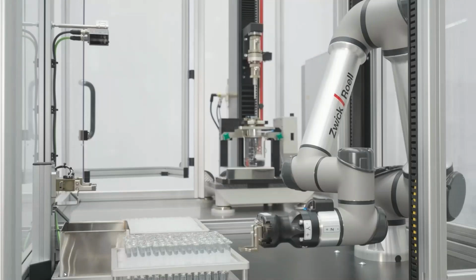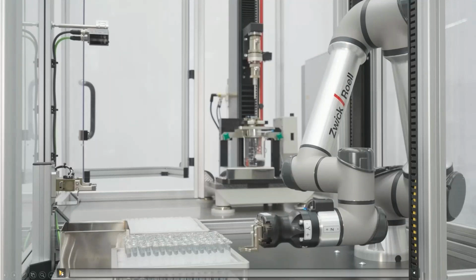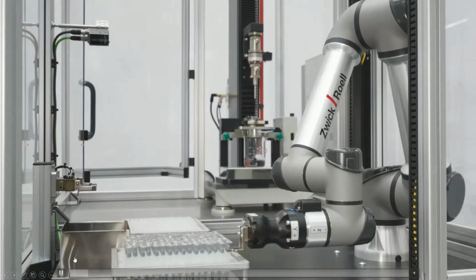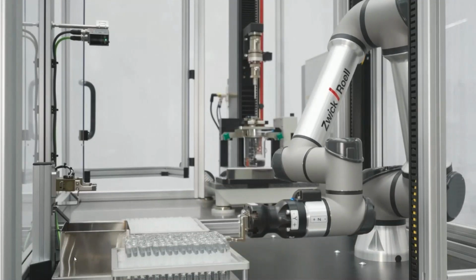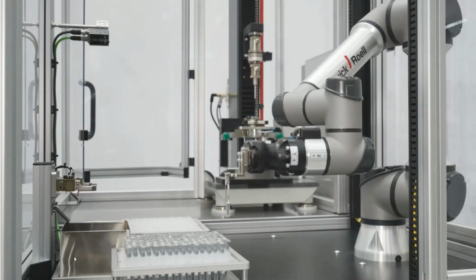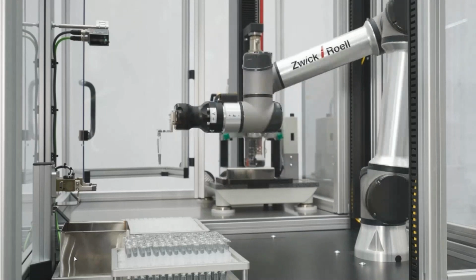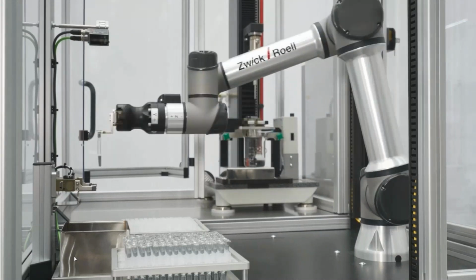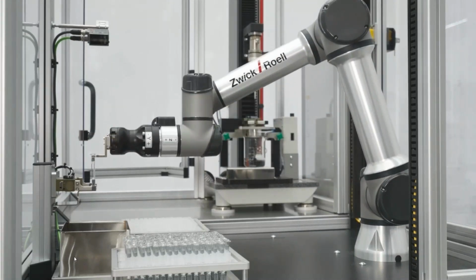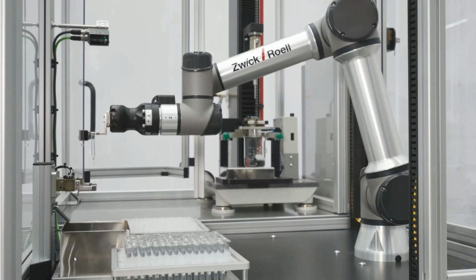So what's the summary of all? So we're coming to an end. Oh no, I brought the last example with me. Sorry, I forgot it. This is the testing of break loose gliding force. Here we're having the prefilled syringes. So we are picking out the sample here. We are then moving towards the cap removal. So we are removing the cap.